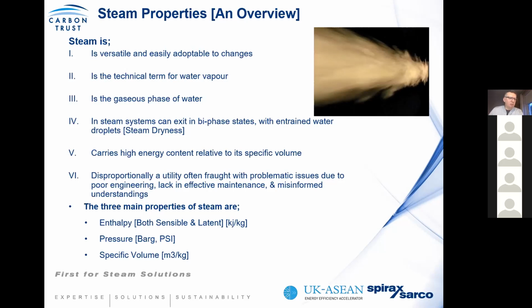It wants to give up its high energy content by condensing. We also have steam at different pressures. We'll be talking about why you could select the pressure for your application. And importantly, we talk about specific volume, because when it comes to steam systems, the higher the pressure, the lower the volume, which means you can get large volumes of steam for smaller sized pipes, which helps with the installation costs.